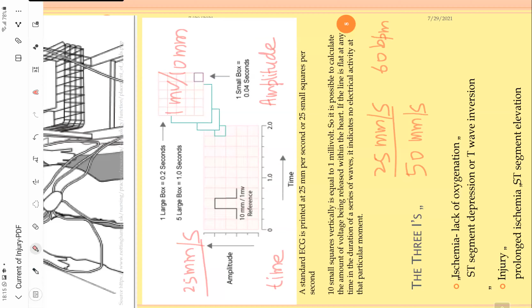No, because it was a wrong calibration with which the machine was set, which has caused an error in recording. The patient's heart rate is 60, but your ECG is showing it as 30 beats per minute. This is because you have set it in a wrong way. So that's why it becomes important every time you see an ECG to check what calibrations have been set by the recorder. Sometimes ECG can automatically change these parameters, the speed and voltage both.